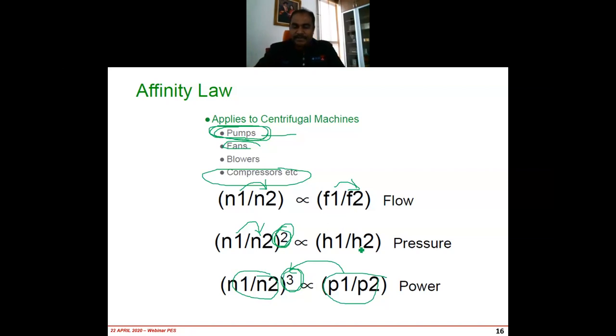I will show you some case studies where we have tested this, just to give you actual data. When we reduce the speed a little bit, for example, if the motors are always running at 50 hertz all the time and we just reduce it to, let's say, 45 or even 46, that means a reduction of 4 hertz, we see a very huge reduction in the power. Because most of the systems are pump and fan systems, which comply, and this affinity law is always true. That gives us another motivation: if there is a need to change the speed, like the case of the pump system just now, we should find a way to reduce the speed by using the variable frequency drive, because there could be a huge amount of savings in the power, and eventually the energy.